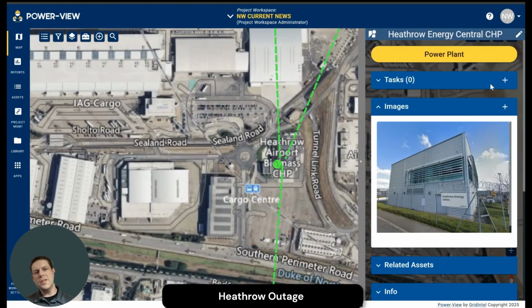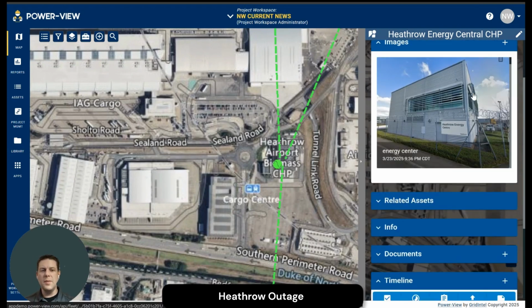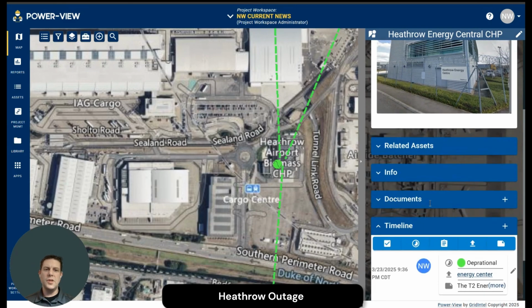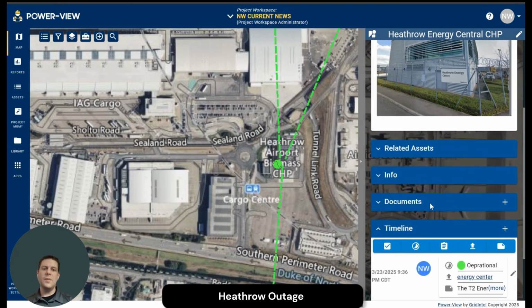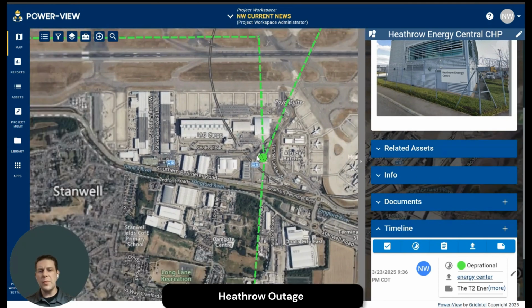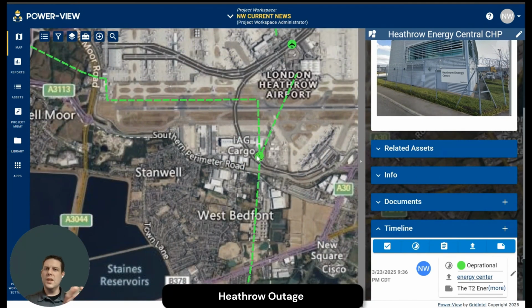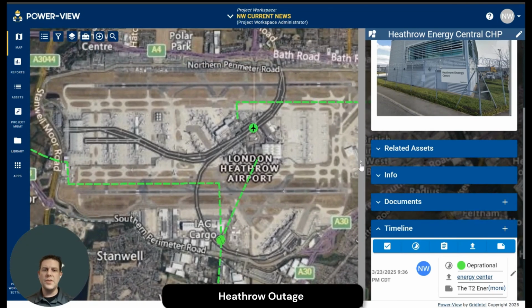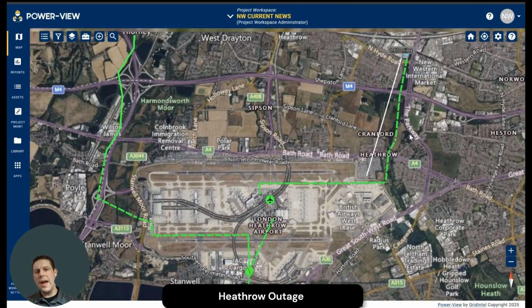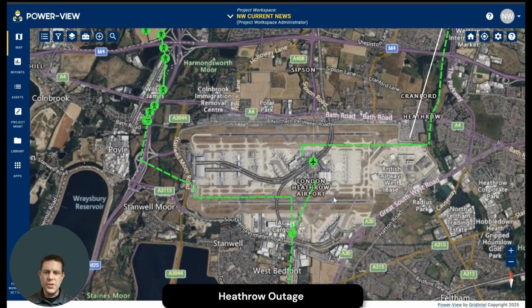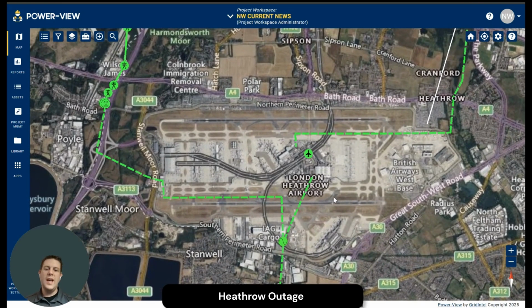This is Energy Central, CHP - combined heat and power. Whether or not there's enough generation there, I doubt it, which is why it has these different substations. From a resiliency standpoint, you not only have to keep the substations feeding critical systems resilient with N-1, N-2 contingencies, but also the distribution system itself. So even though this event occurred right at North Hyde substation, there are three sources of power feeding this airport, as well as, possibly, an on-site power plant for combined heat and power to the electrical system.